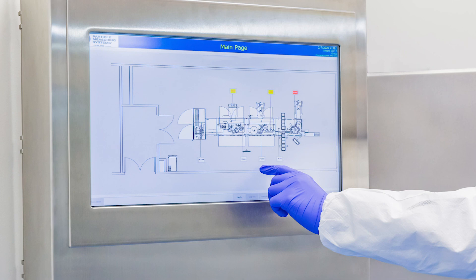My last question: how is the ISO-Air Pro-E typically used? This is an aerosol particle counter specifically focused on the life science market. Those types of counters have to be able to measure 0.5 and 5 micron. In addition, some applications may require other channels — this system is capable of having up to eight different channel sizes that are user selectable. Typically the data from these systems needs to go back to a facility monitoring or environmental monitoring system, which gathers the data, presents reports, and turns on light towers. We designed this system to work with our own Facility Pro or Pharmaceutical Net Pro software and control systems, and also to have Modbus capabilities output.